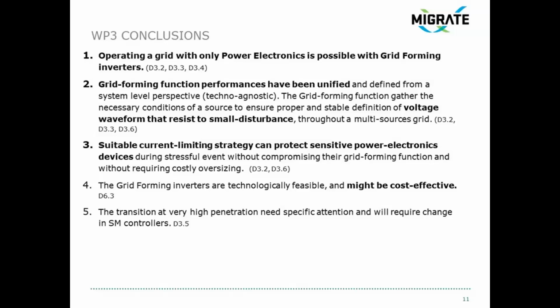So we know that grid forming inverters are technologically feasible, at least from a small scale, and as Julian said, we have demonstration also for a wind farm, tens of megawatts, that operated for a few months in grid forming. We also carried out a cost analysis and compared grid forming inverters to a synchronous condenser on a French scenario. It was for 2035, and we ended up with costs that were roughly the same.